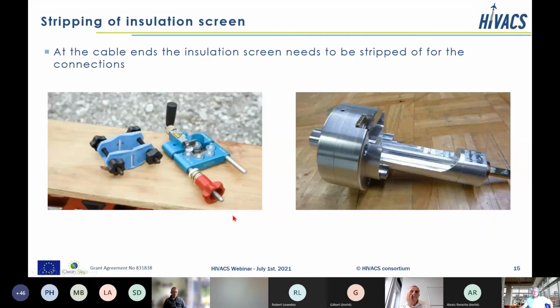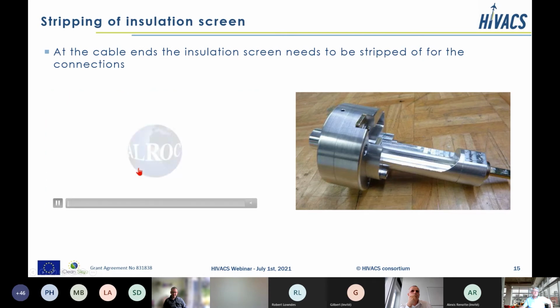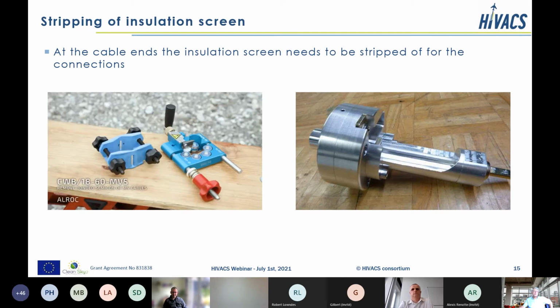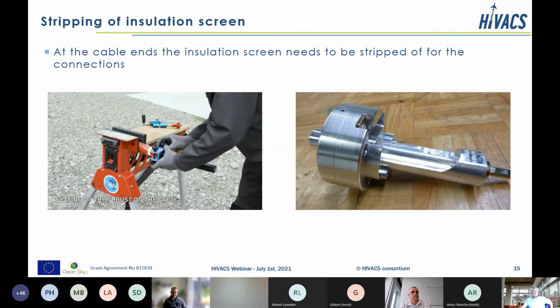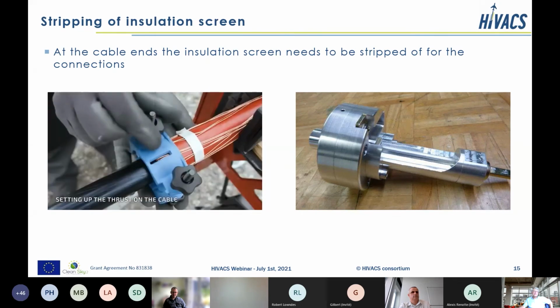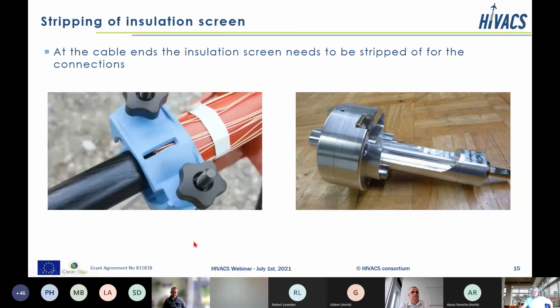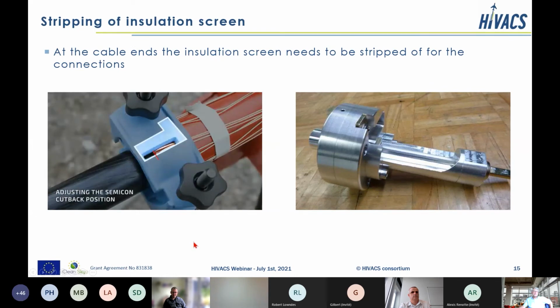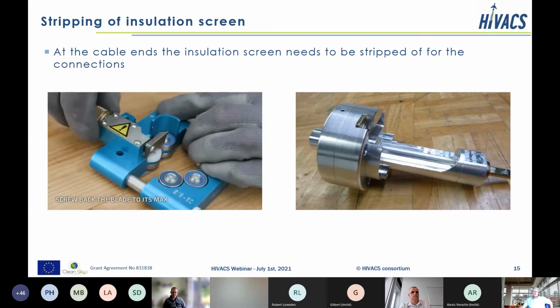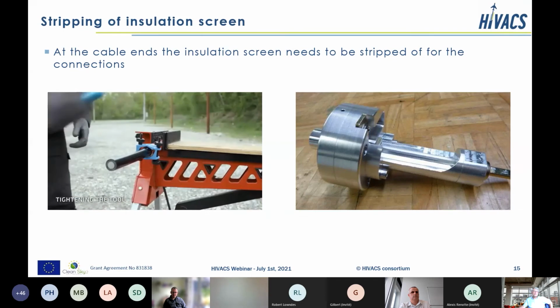As those 3 layers are tightly bonded together, you can't peel them off from the insulation like a banana skin. So you need some specific tools. Here we have a specific tool which is suitable for a wide range of diameters. The disadvantage is that the setup of the tool takes some time, because you have to adjust it to the diameter of the cable, which is shown here in that short video.